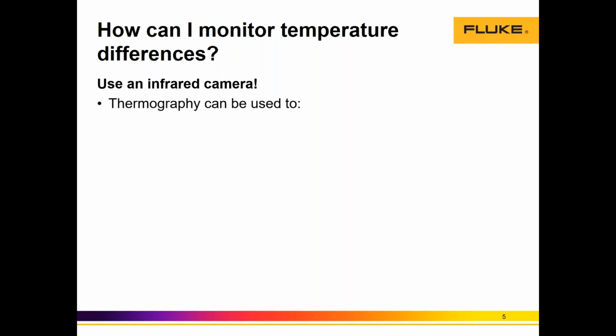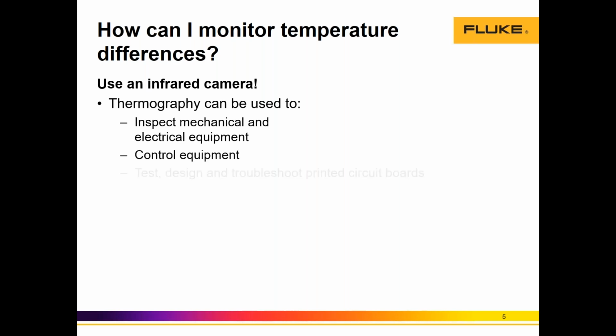So we might find questions about equipment conditions that are often raised by abnormal indications, as I mentioned before. Examples could be a motor bearing, which is significantly warmer, and obviously we cannot see that visually. So we need a thermal camera to detect the heat signature on the area, right? It could also be a hot bushing or a tap in the transformer, right? Other assets such as MCCs, internal component failures, with thermal cameras we should be able, through isolated heat signatures, to detect these issues through thermal indications, right?